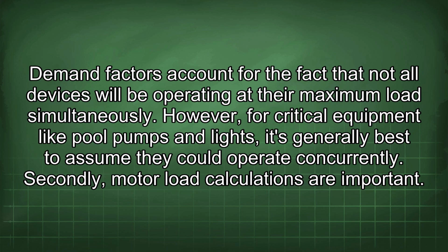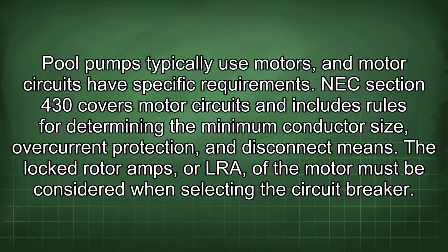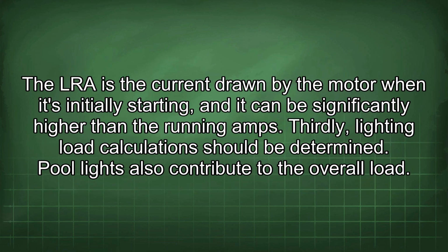However, for critical equipment like pool pumps and lights, it's generally best to assume they could operate concurrently. Secondly, motor load calculations are important. Pool pumps typically use motors, and motor circuits have specific requirements. NEC Section 430 covers motor circuits and includes rules for determining the minimum conductor size, overcurrent protection, and disconnect means. The locked rotor amps, or LRA, of the motor must be considered when selecting the circuit breaker.